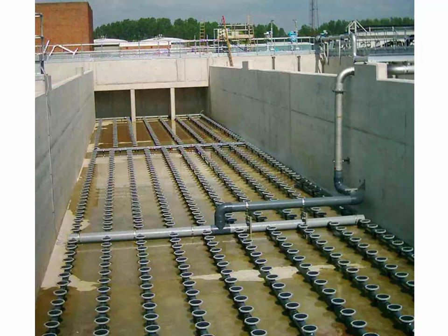So the big bubbles are bad because they just float to the top really quickly and the oxygen can't get into the water. But if you have tiny little bubbles, they float to the surface really slowly, and because they're so small, it's easy for the oxygen to get into the liquid. So that's what we're trying to achieve with these diffusers, the smallest bubble size that we can get. The problem is that membranes that give you a small bubble size require a lot of maintenance. And so it's like a balancing act.